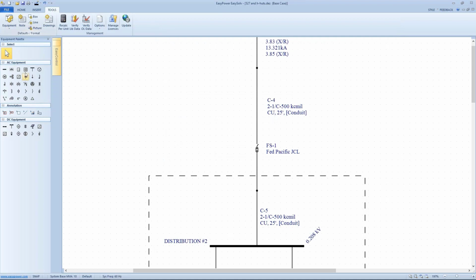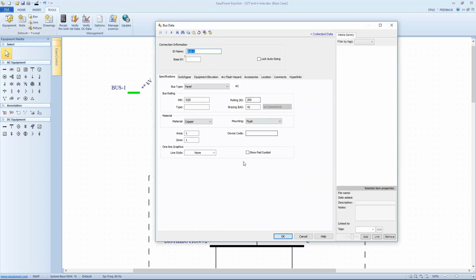Now, if most of my buses are going to be panels, let's say they're square D panels, I might want to set up my default value to be square D. And let's say I know they're all going to be 200 amp panels, and I know from the data sheet that they're braced or set up for 42K, and they're copper material, and they're going to be freestanding or flush mounted. So if this is what a majority of my panels will be, by setting up this default, when I add another element now to my one line and I go in and look at the data dialog box, it'll have all those values in there.